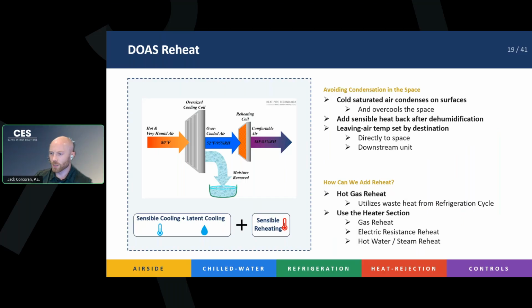And we talked a little bit about the different ways to do reheat. Hot gas reheat is probably one of the more common ways to do it. If you have a DX system or a refrigeration cycle, you're going to be able to recover that heat from the compressor discharge, and it's free, right? You already have that heat in the system from the space. Your refrigerant is just redirected downstream to a second coil, which is where we reheat the air. Or you can just use electric resistance. You can use hot water, steam, or gas. Really, any source of heat is possible to use for your reheat. However, hot gas reheat a lot of the time just comes bundled in with your unit and you don't have to think about sizing it.